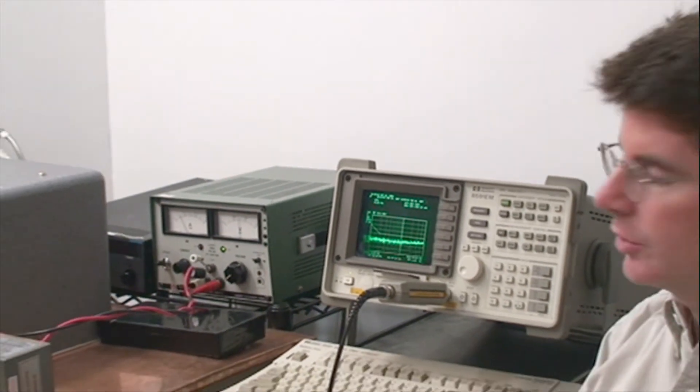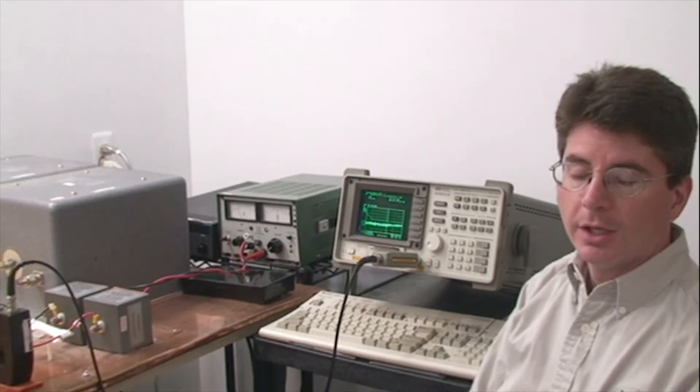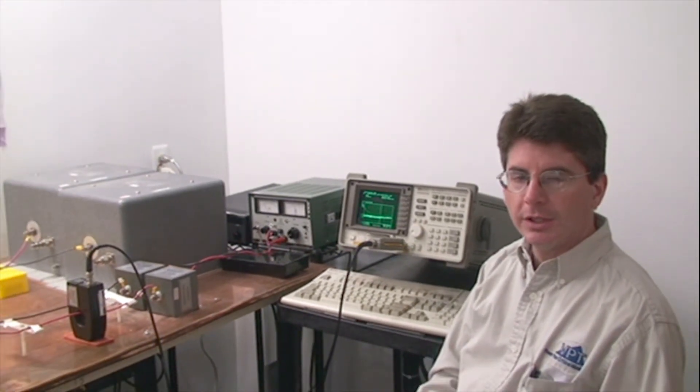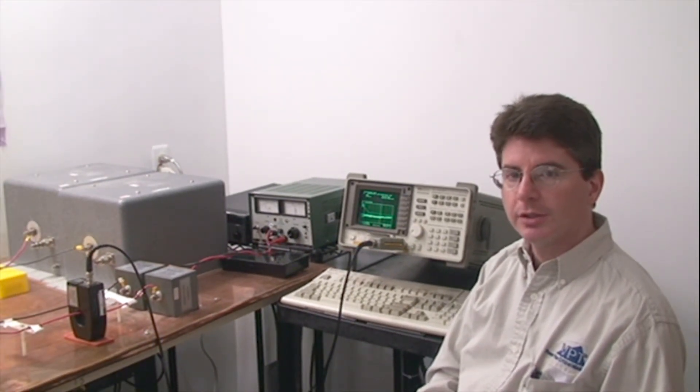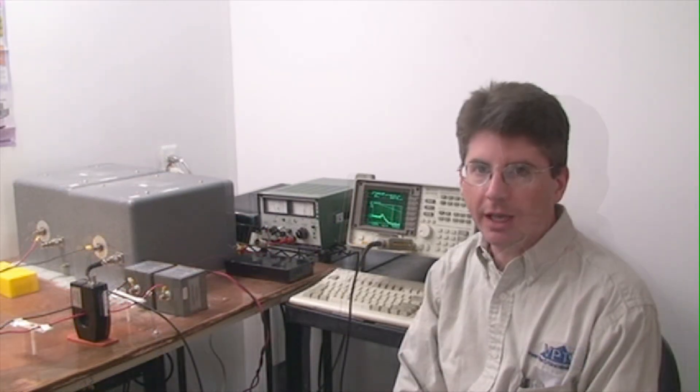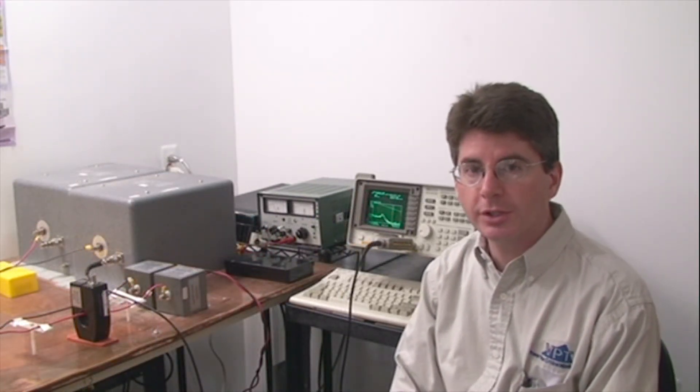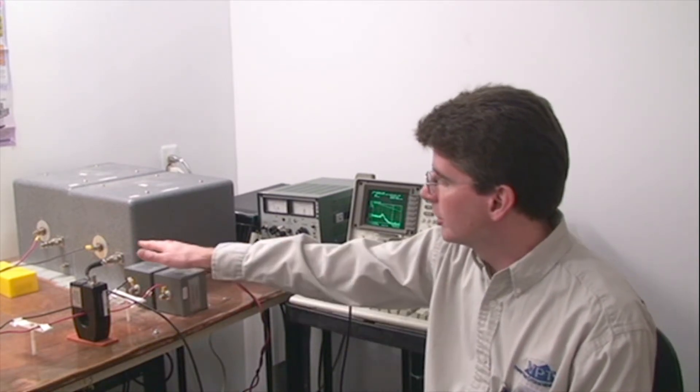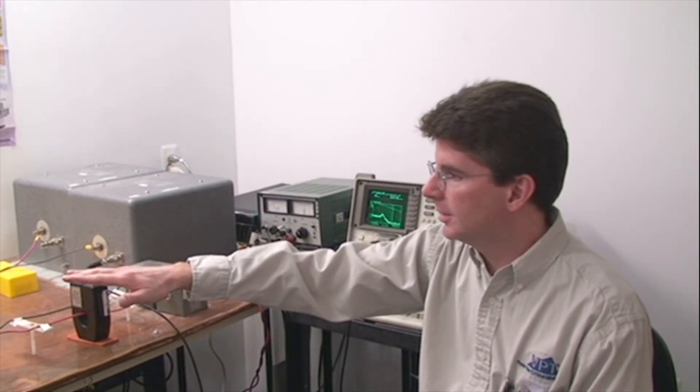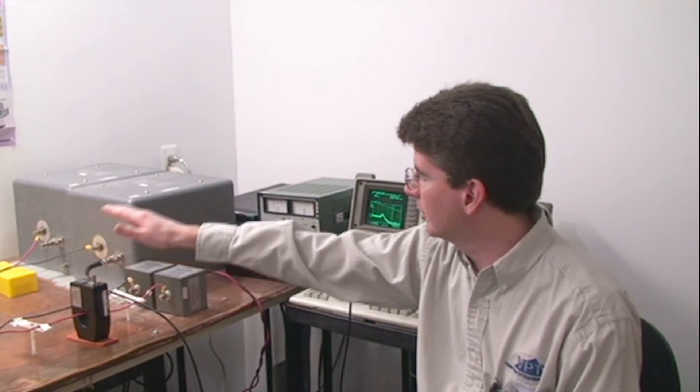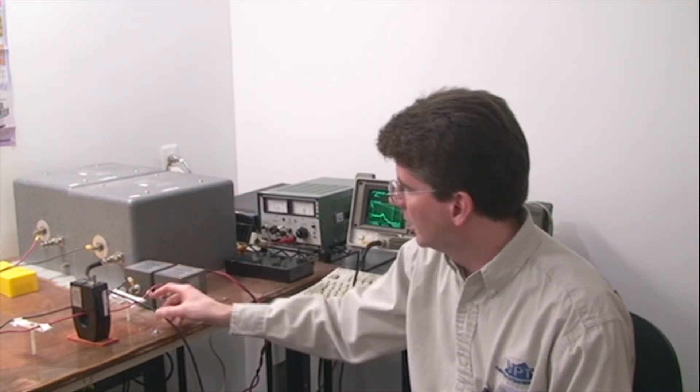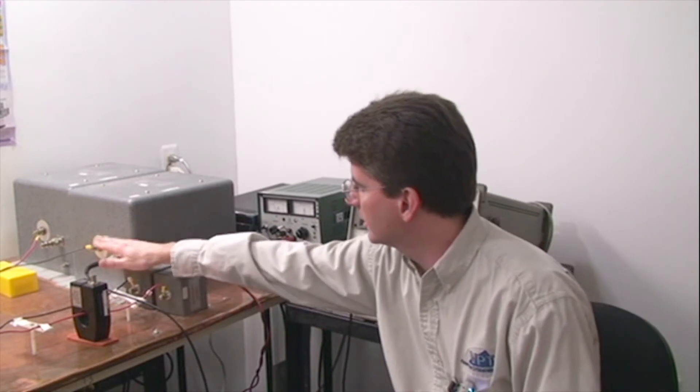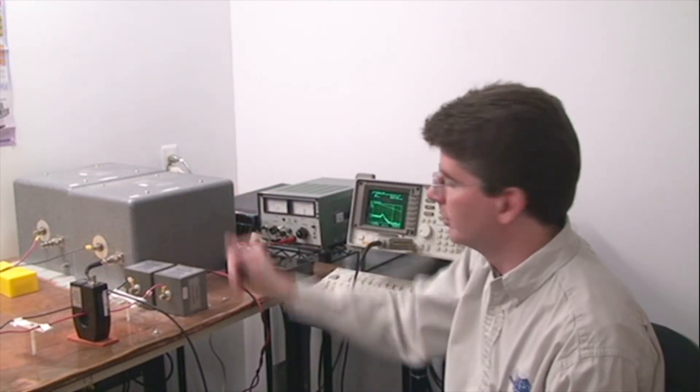Now we will change our setup over to MIL-STD-461DEF setup using the LISNs. So we've moved the DC-DC converter and EMI filter over to the LISN side. We've connected the EMI analyzer to the LISN. And we've also moved the power source.